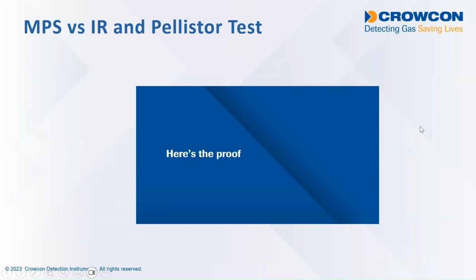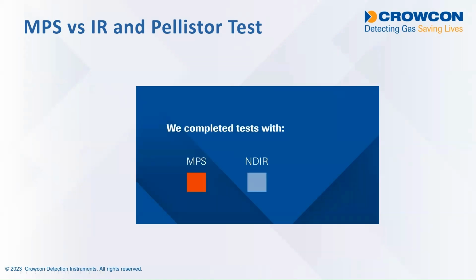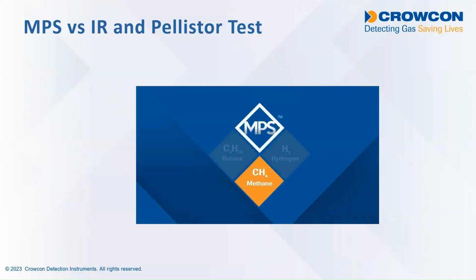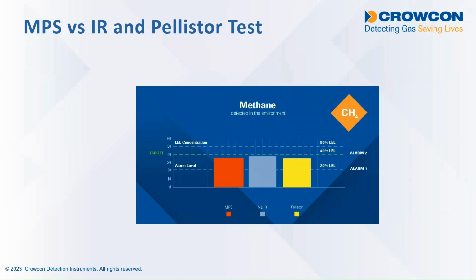So this short animation shows test data which proves that the MPS sensor outperforms the Pellistor and the infrared gas detector in a scenario where we have exposure to different gas concentrations. Here we have test data with methane applied to all three different technologies of sensor that have been calibrated with methane. So you can see they all respond accurately to methane: the MPS, the NDIR, which is the infrared sensor, and the Pellistor. If the same sensors are then exposed to butane, you can see that the infrared sensor gives a huge overread. The Pellistor is a bit inaccurate, whereas the MPS sensor remains accurate. And if hydrogen is then exposed to the sensors, again, the MPS remains accurate, the Pellistor underreads, and the infrared detector doesn't measure hydrogen at all.